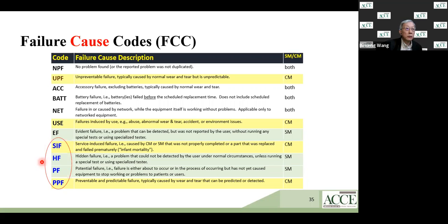Hidden failure is something that is even more problematic because this is something that the user does not know about. In the past, this was very common. Nowadays, it's becoming less and less common because most manufacturers have built-in error detection software in the devices that alert the user that, hey, there's something wrong here, do not use me. And this is not just for the protection of the patient or even the user, but in the United States, this is used primarily by the manufacturer to protect themselves against lawsuits. Here we have a tendency of having too many lawyers, and they just go and sue everybody whenever somebody gets harmed. And the manufacturer will use this to protect themselves, saying, hey, my machine told you that it has a problem and you still decided to use it. And therefore, it's not our fault that the patient got harmed.